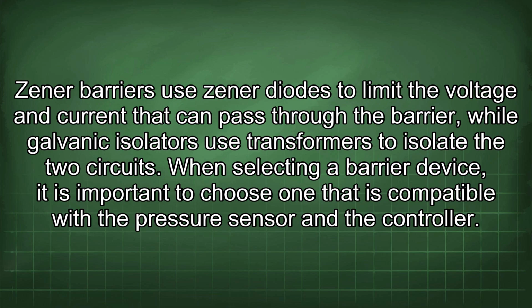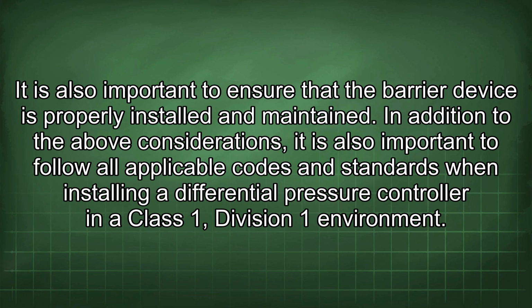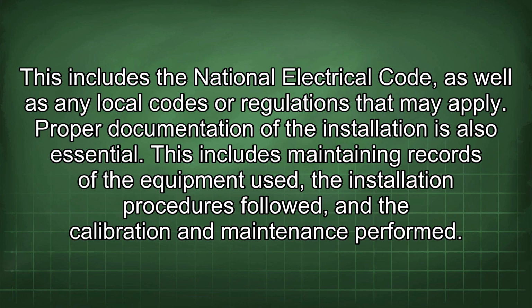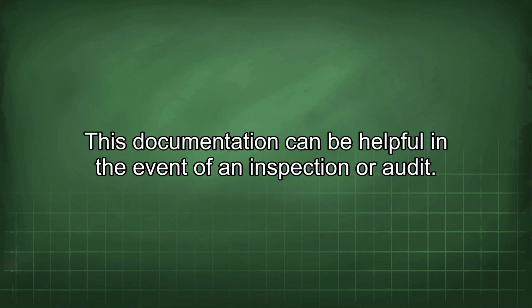When selecting a barrier device, it is important to choose one that is compatible with the pressure sensor and the controller. It is also important to ensure that the barrier device is properly installed and maintained. In addition to the above considerations, it is also important to follow all applicable codes and standards when installing a differential pressure controller in a Class 1, Division 1 environment. This includes the National Electrical Code, as well as any local codes or regulations that may apply. Proper documentation of the installation is also essential. This includes maintaining records of the equipment used, the installation procedures followed, and the calibration and maintenance performed. This documentation can be helpful in the event of an inspection or audit.